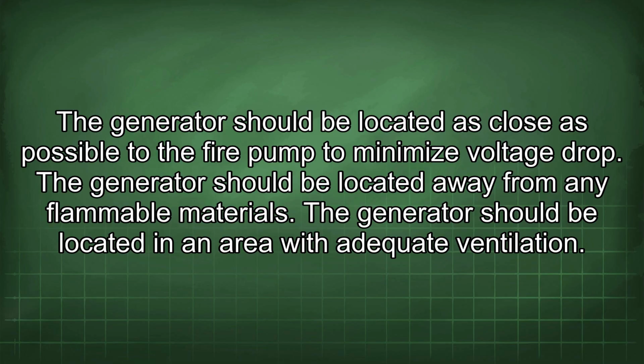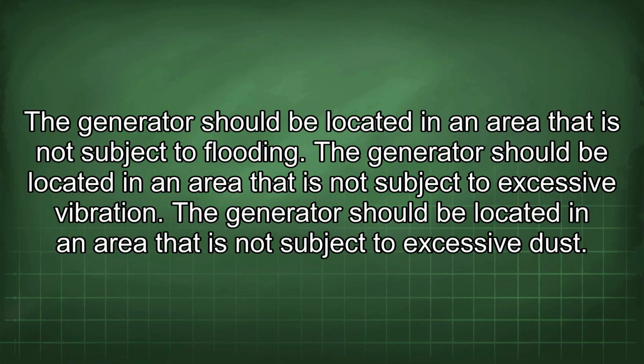The generator should be located as close as possible to the fire pump to minimize voltage drop. The generator should be located away from any flammable materials. The generator should be located in an area with adequate ventilation. The generator should be located in an area that is not subject to flooding, excessive vibration, or excessive dust.